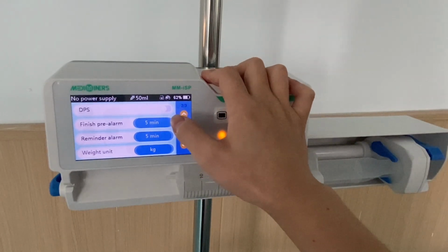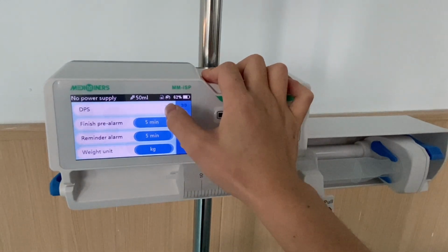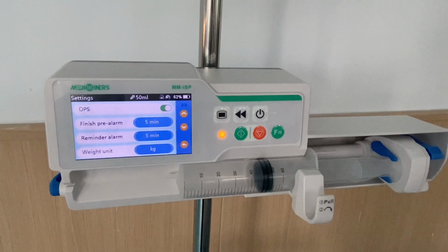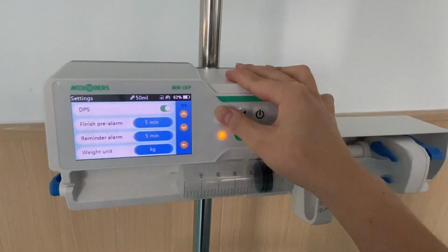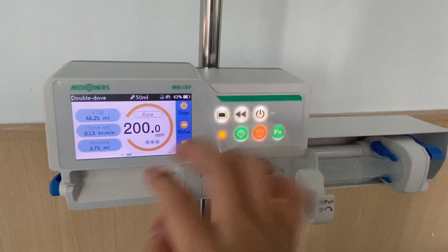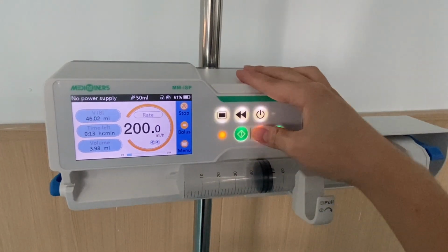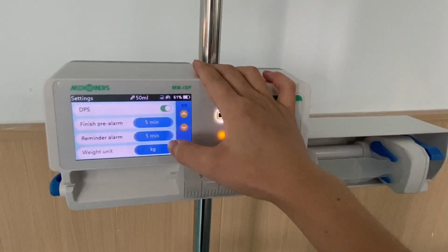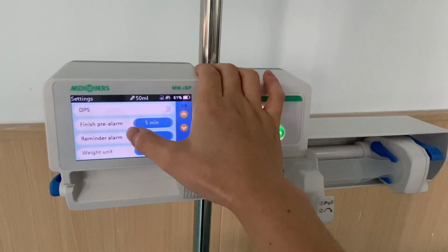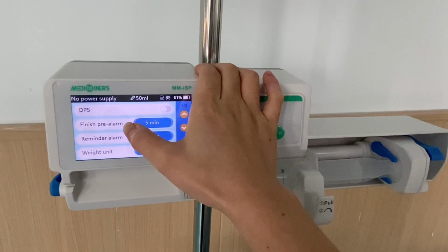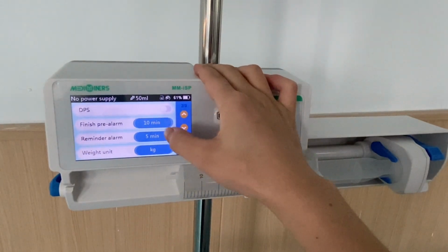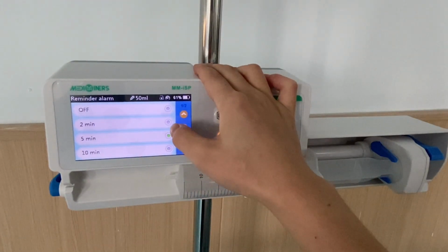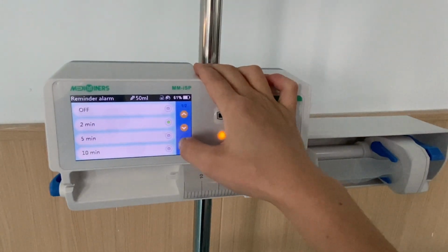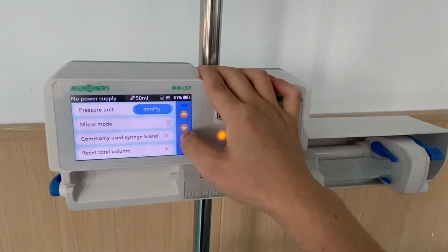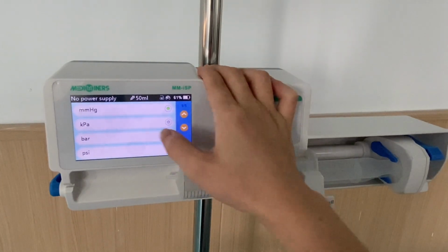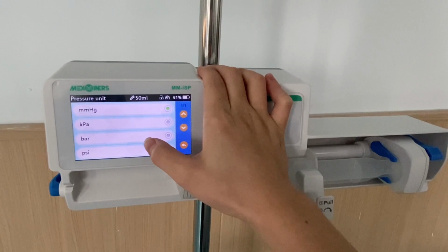And the DPS means dynamic pressure system. If we want to use this, we just activate it. You can see the real-time pressure shown on the screen. Let's go back to the settings. The finish pre-alarm is to remind the nurse or doctors that the infusion is about to finish. We can set any time you want to remind you. The reminder alarm is the same. You can choose the time you want. And the weight unit, we have different units. For pressure unit, we have 4 kinds: millimeter of mercury, kPa, bar, and PSI.